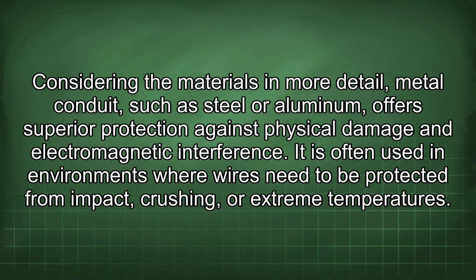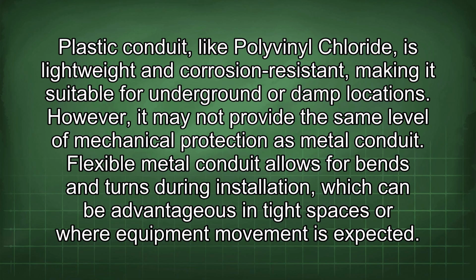Considering the materials in more detail, metal conduit, such as steel or aluminum, offers superior protection against physical damage and electromagnetic interference. It is often used in environments where wires need to be protected from impact, crushing, or extreme temperatures. Plastic conduit, like polyvinyl chloride, is lightweight and corrosion-resistant, making it suitable for underground or damp locations. However, it may not provide the same level of mechanical protection as metal conduit.